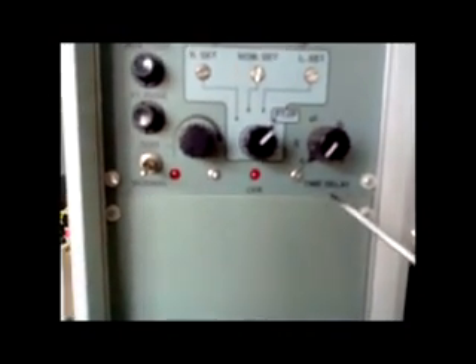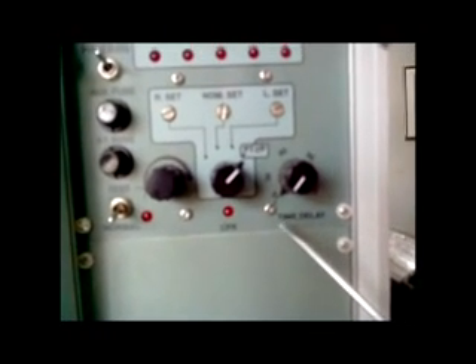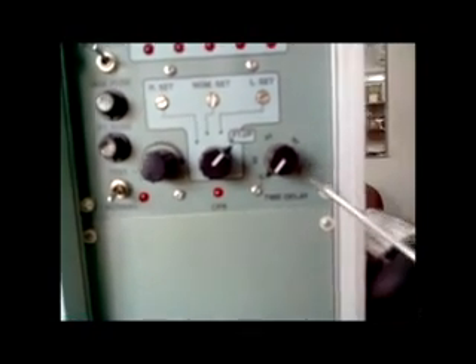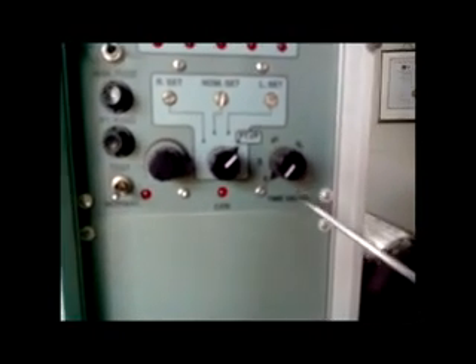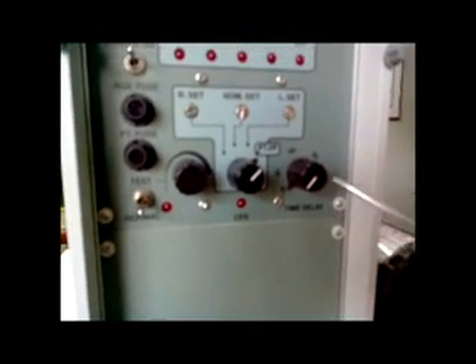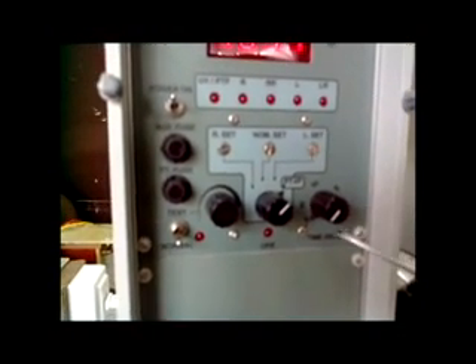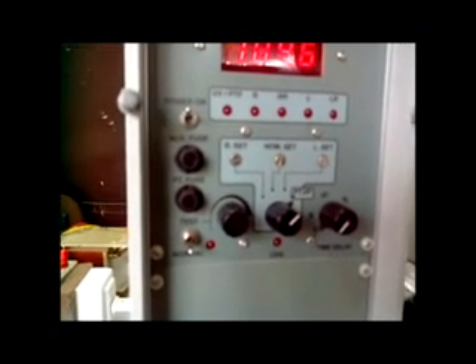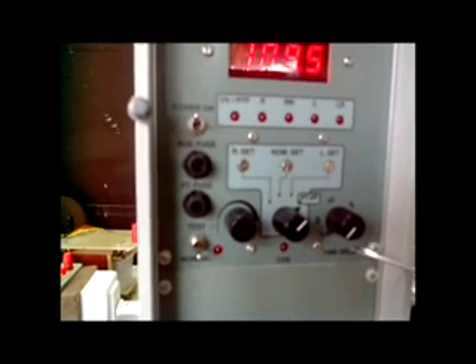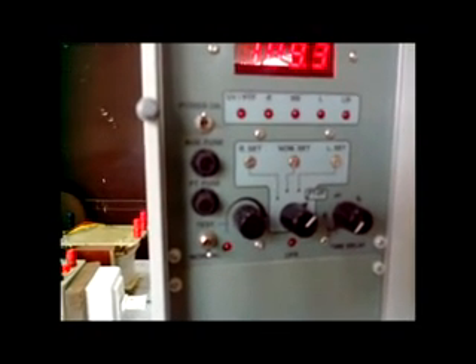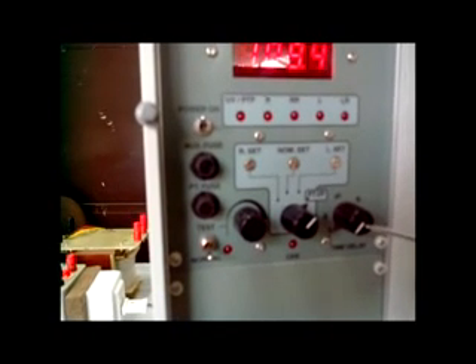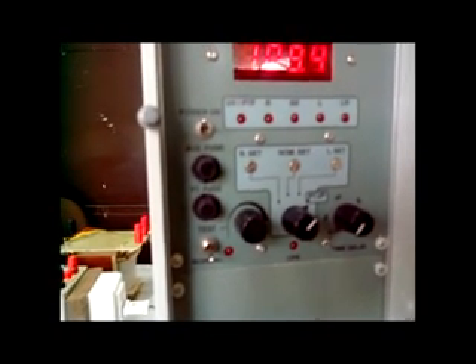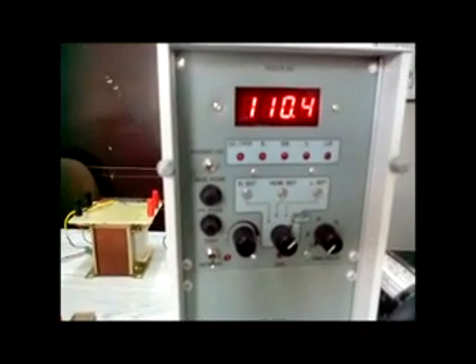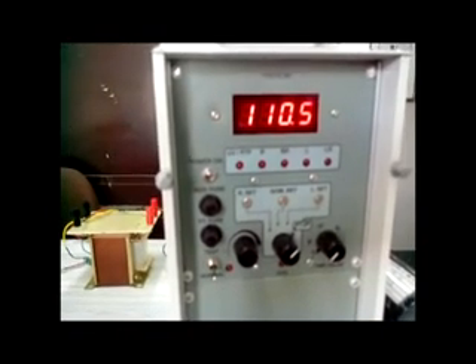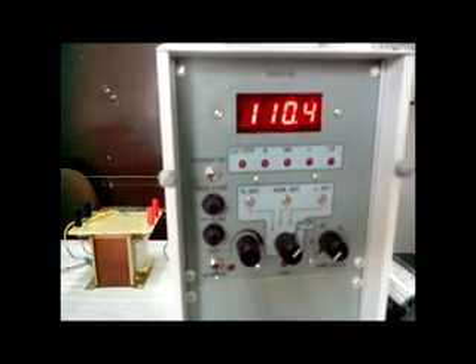After the 3 settings, we have to set the time delay setting. We can see the time delay setting is 10 seconds to 120 seconds. This time delay operates when PT voltage is beyond the band voltage; then the time relay operates to delay RR and LR. This time delay setting should be more than each tap change operation cycle time on the on-load tap changer. Now we will see the operation of RR. Now we will change the PT voltage and see the actual operation of the regulating relay.